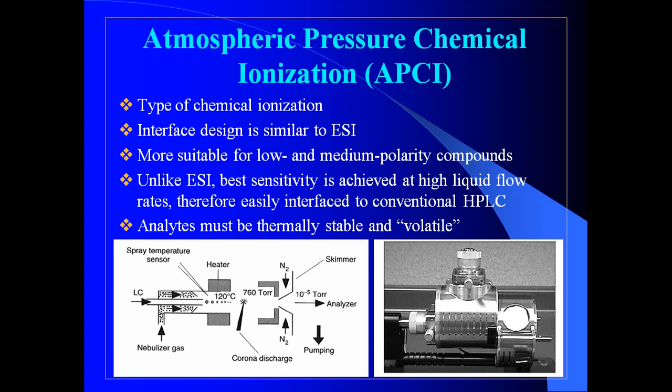The primary ions, which are formed as a result of this discharge, are converted by collision processes to the final ion molecule reaction products. The operator can set the corona discharge as desired at the application computer by adjusting the value of the needle current.